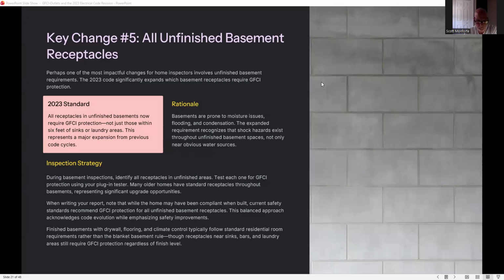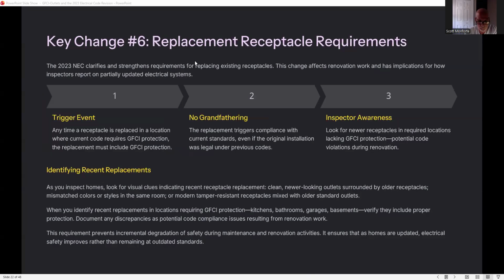Finished basements with drywall, flooring, and climate control typically follow standard residential room requirements rather than the blanket basement rule, though receptacles near sinks, bars, and laundry areas still require GFCI protection regardless of finished areas. Basically, if you're in an unfinished basement, every receptacle's got to be GFCI.